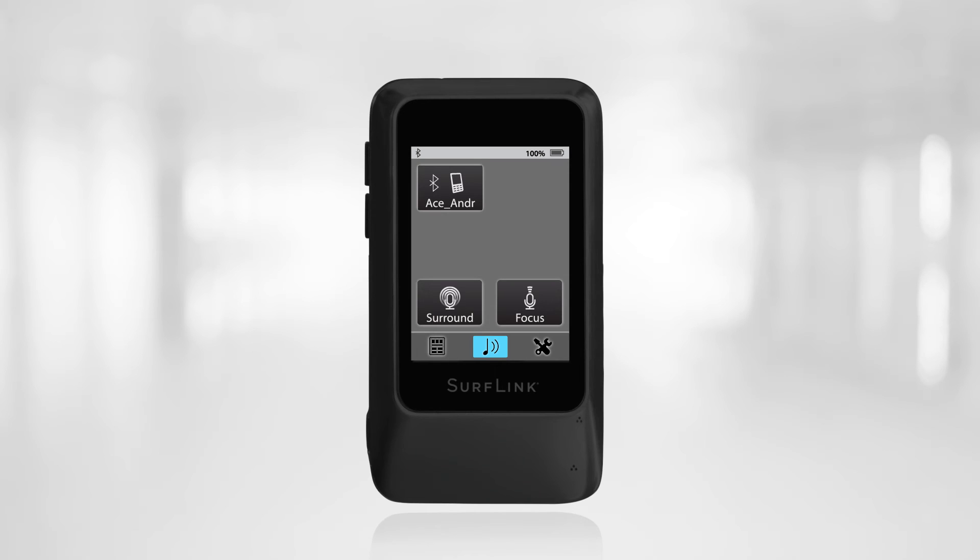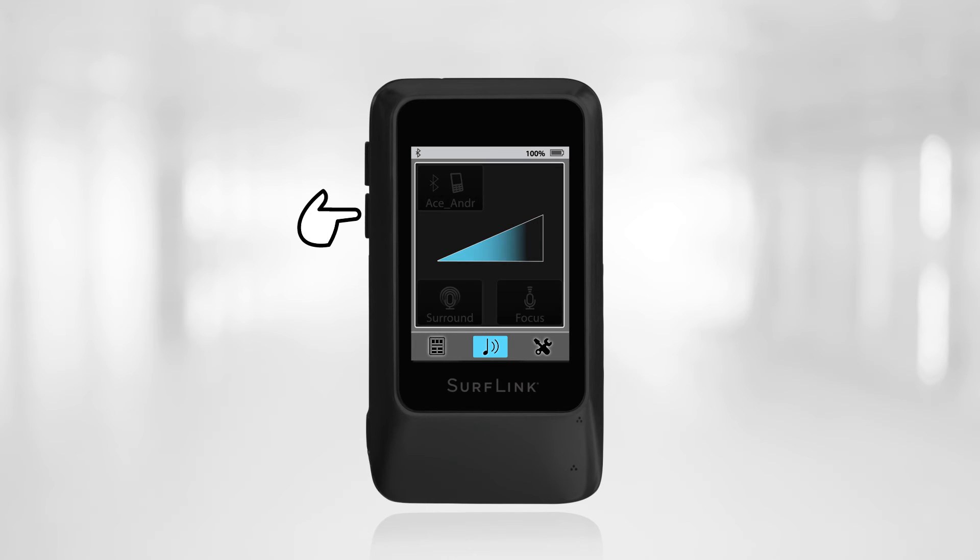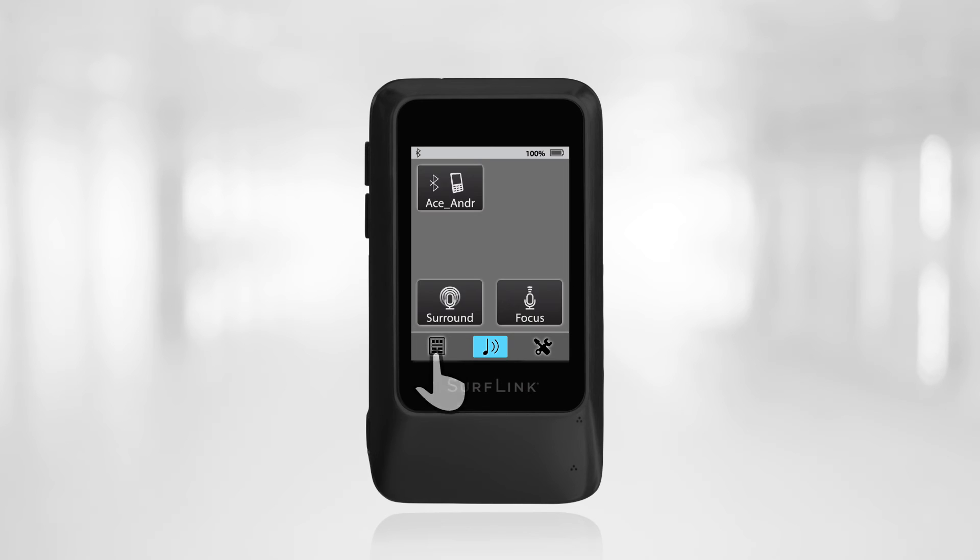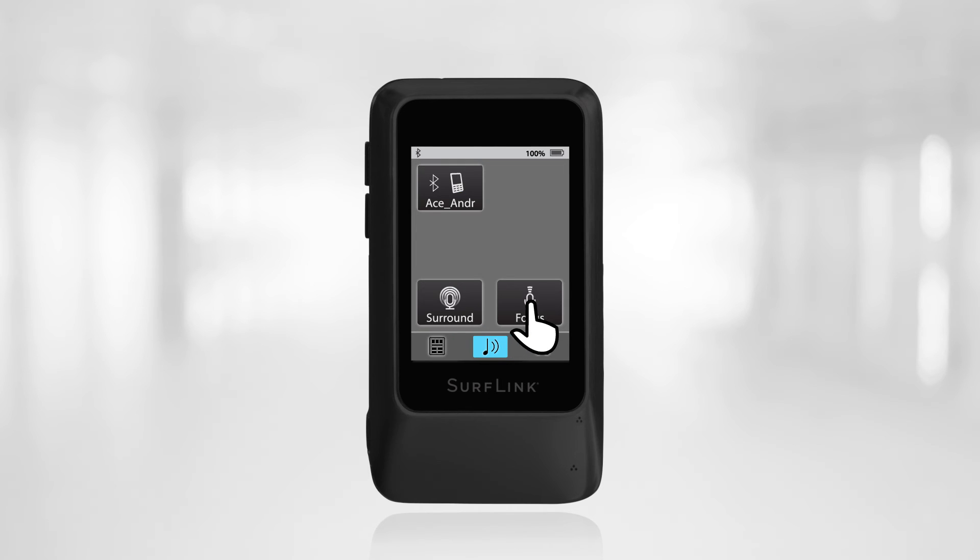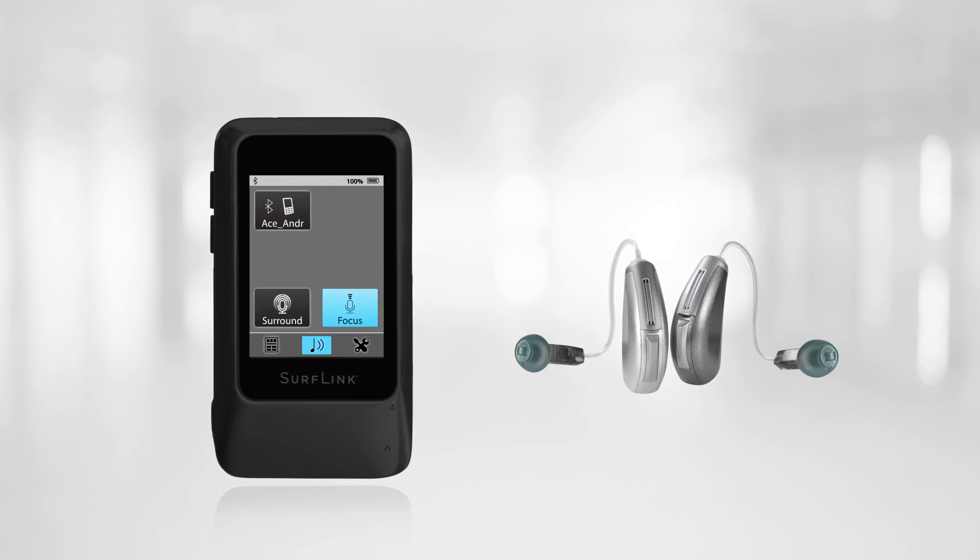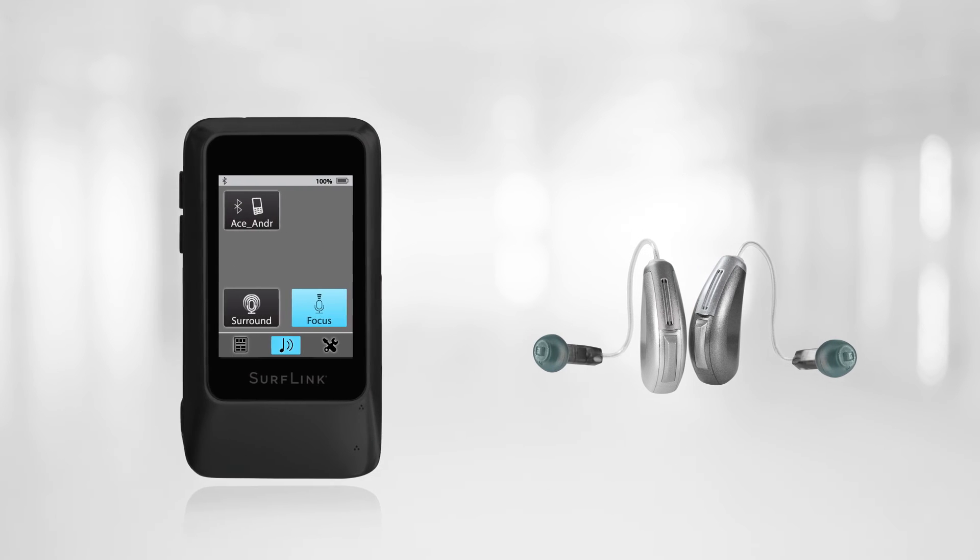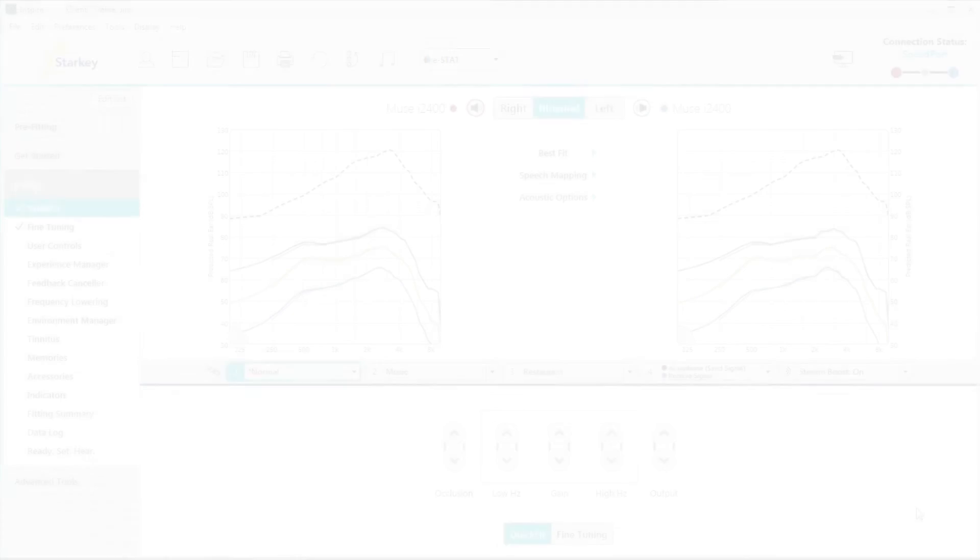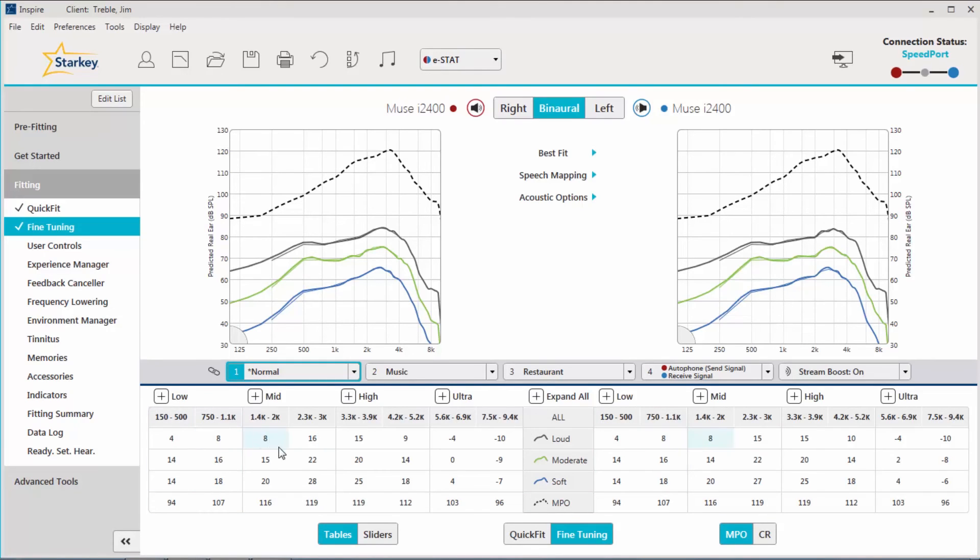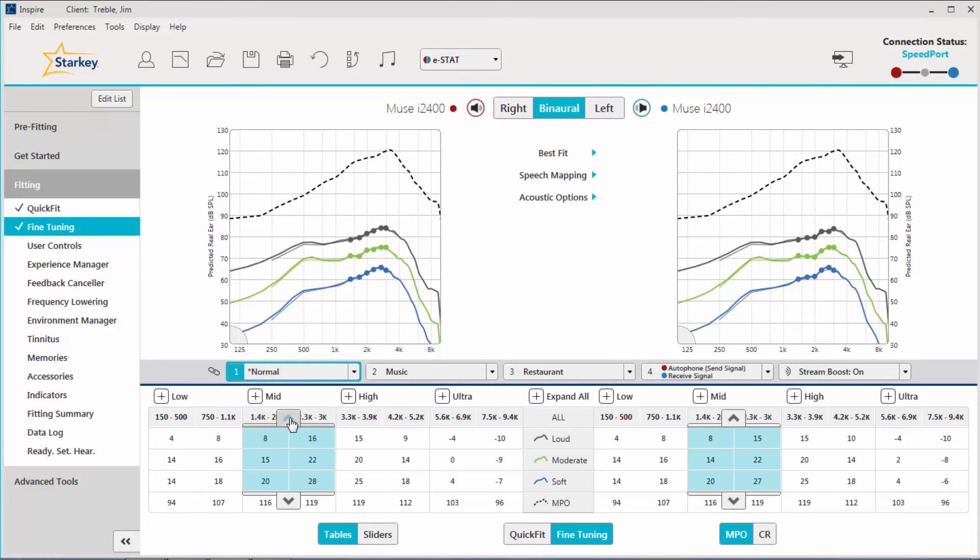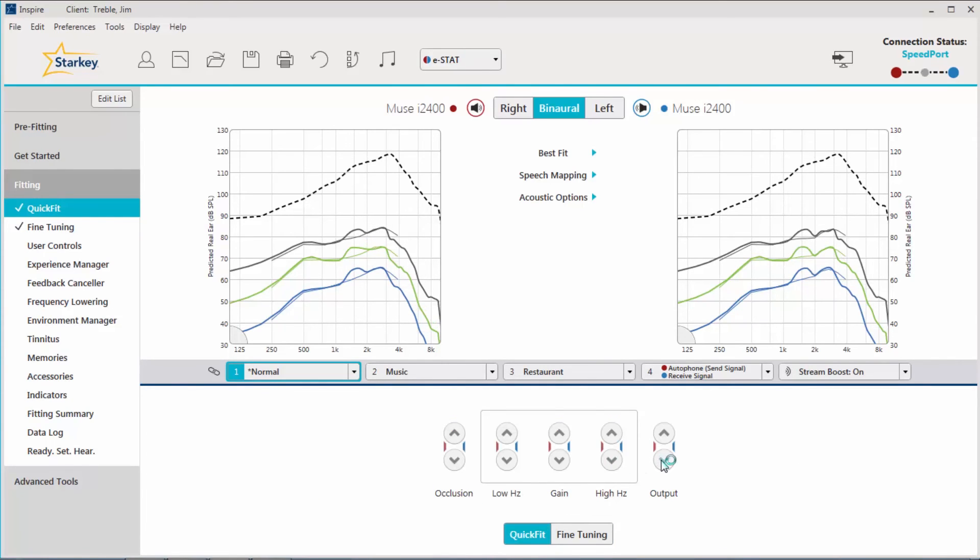Lastly, when using the remote microphone function of the SurfLink Mobile 2, there may be occasional instances of static. Possible solutions include turning down the hearing aid volume or muting the hearing aids completely while streaming from the remote microphones. Increasing the distance between the hearing aids and the SurfLink Mobile 2 can eliminate the occasional static. Finally, adjustments with Inspire 10 could also solve the static issue. With the hearing aids connected to Inspire 10, try increasing mid-frequency gain or decreasing gain for high frequencies and the overall MPO.